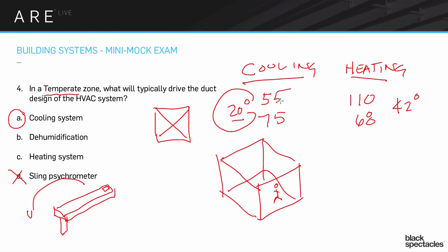So then one question is: why don't I just make, why am I using 55 degree air and not say 35 degree air? And the answer to that is one, it's a little bit harder to make 35 degree air, it's a little expensive, but the real answer is you start blowing 35 degree air into a room where people are trying to work or sleep or something like that and you'll get complaints immediately. Our bodies just don't like air blowing on us that's that cold. Whereas warm air doesn't bother us in the winter. We don't mind having that get blown on us with that big of a difference.